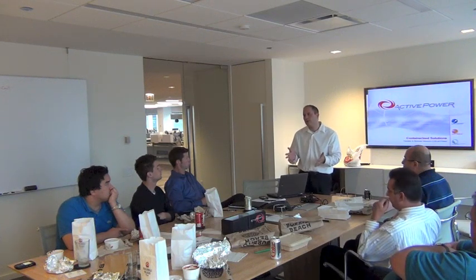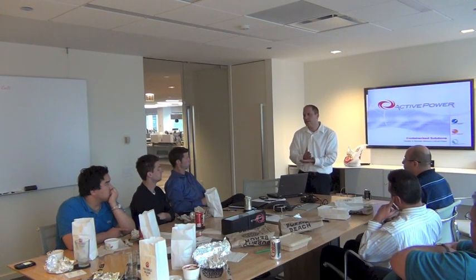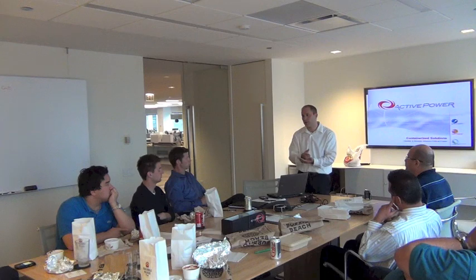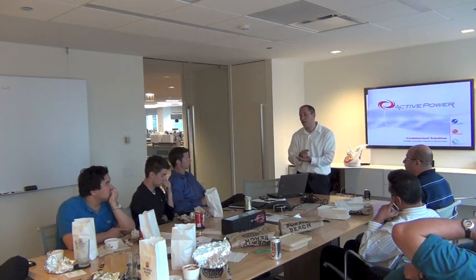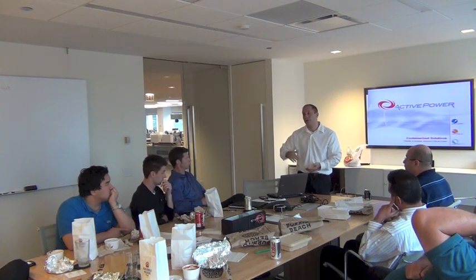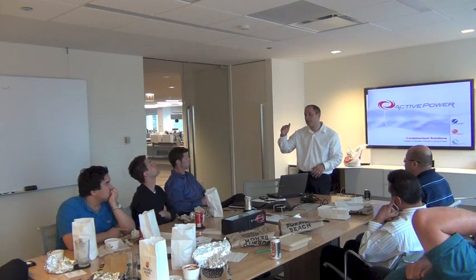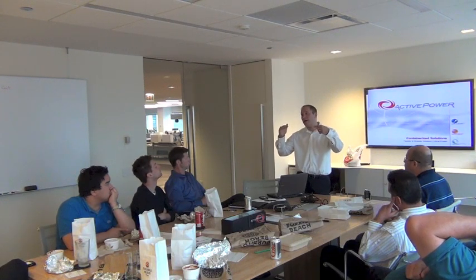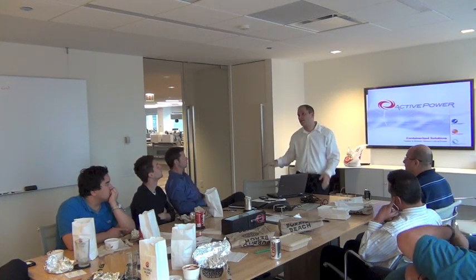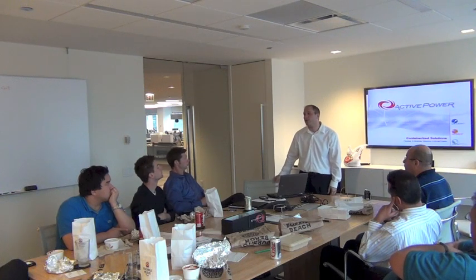But typically, in a typical power sequence, with a 1 second outage or more, you're signaling the transfer switch, or you're signaling a start signal to your generator. Generator comes up to speed and voltage, 9-10 seconds. UPS synchronizes with the generator and walks on the load. Typically, that's 2 to 3 seconds of flywheel energy.